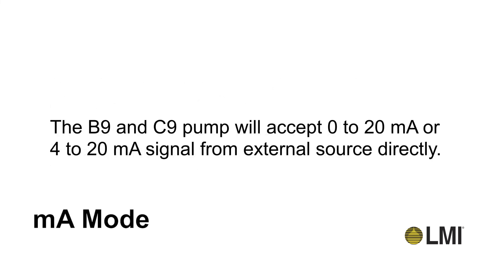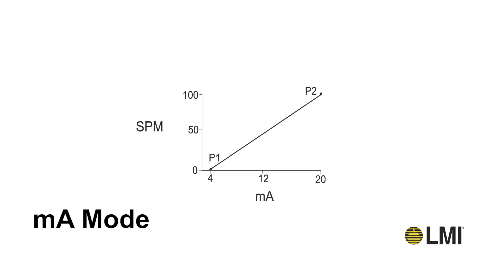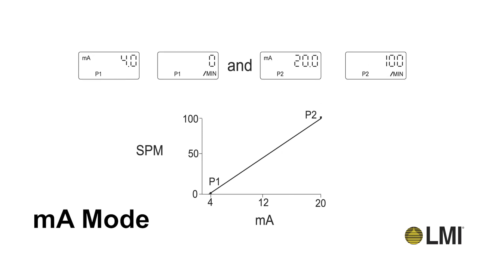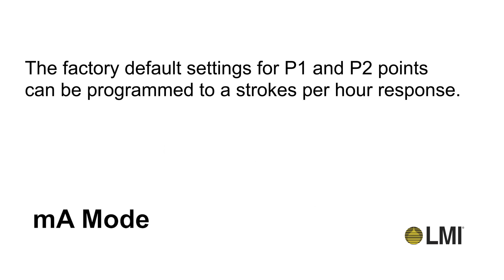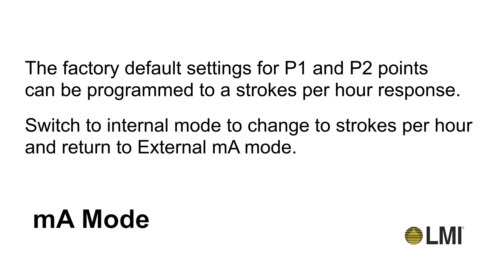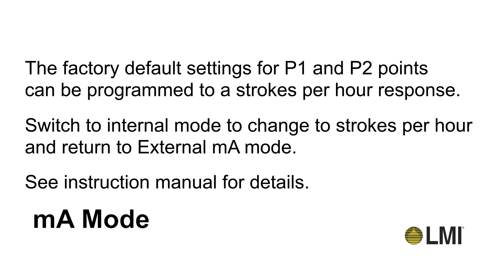The B9 and C9 pump will accept 0 to 20 milliamp or 4 to 20 milliamp signals from an external source directly. The pump's speed is determined by the program response curve P1 and P2. Factory default values are P1 equals 4 milliamps at 0 strokes per minute, and P2 equals 20 milliamps at 100 strokes per minute. The factory default settings for P1 and P2 points can be programmed to a strokes per hour response. Switch to internal mode to change to strokes per hour and return to external milliamps mode. See the instruction manual for details.